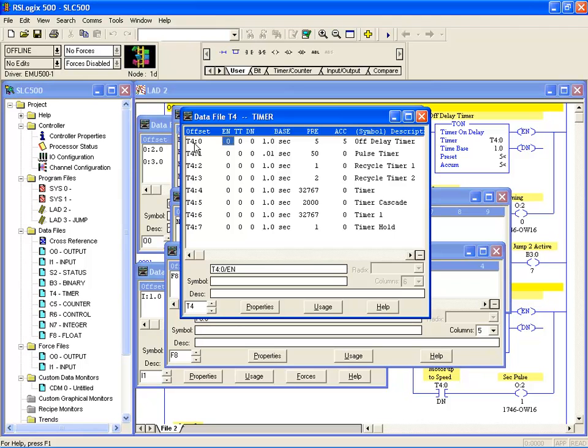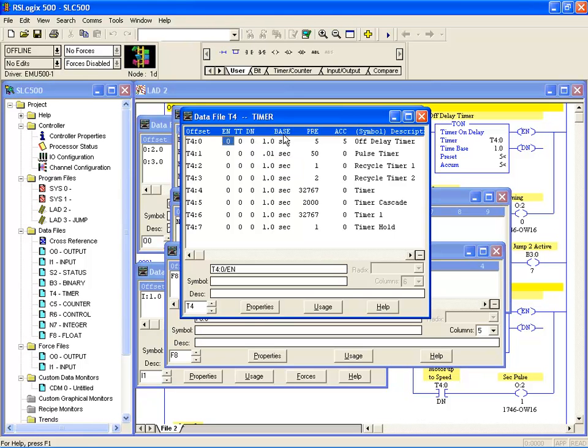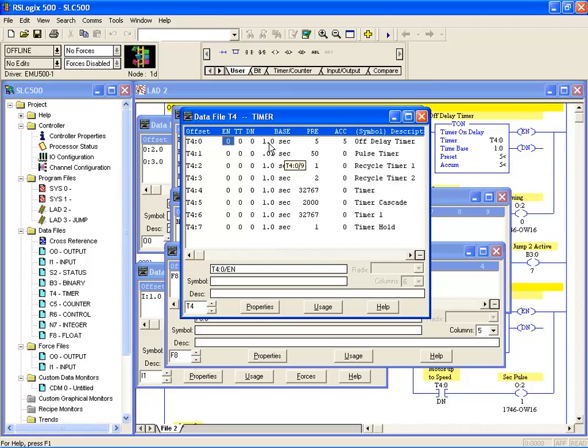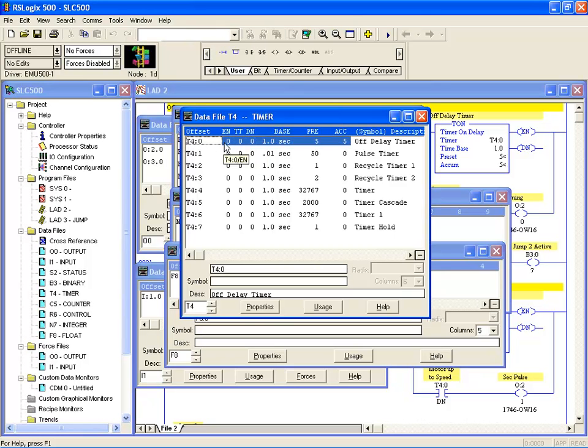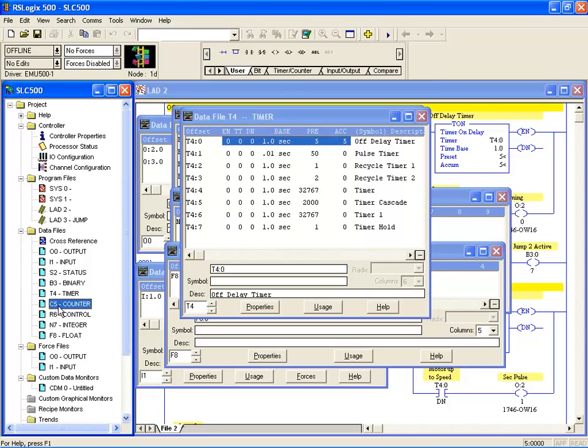If we expand that out, the first one in the row, you'll notice we have the status for enabled, timer timing, and done. We have the time base, then the preset and the accumulator. So one word holds the accumulator, one word holds the preset, another word holds the time base and the status bits. So again there's a three word device makes up this one element. The one timer element is made up of three words. The same applies for a counter.